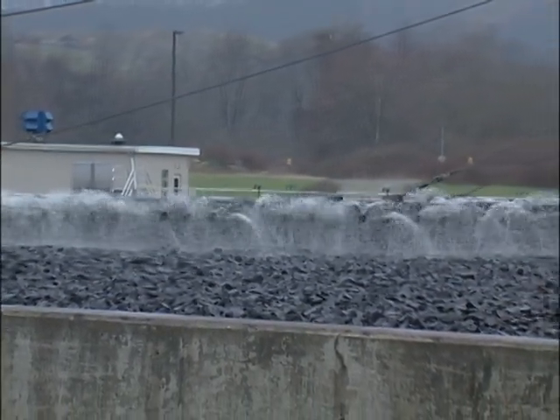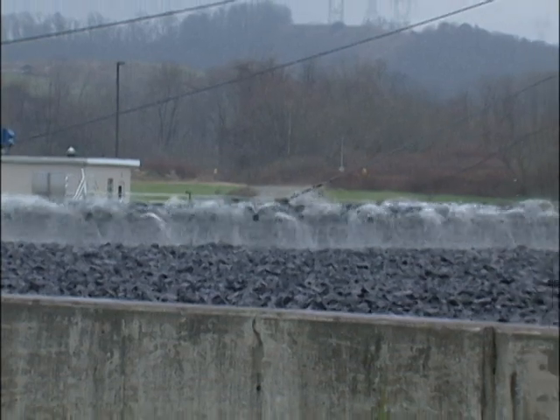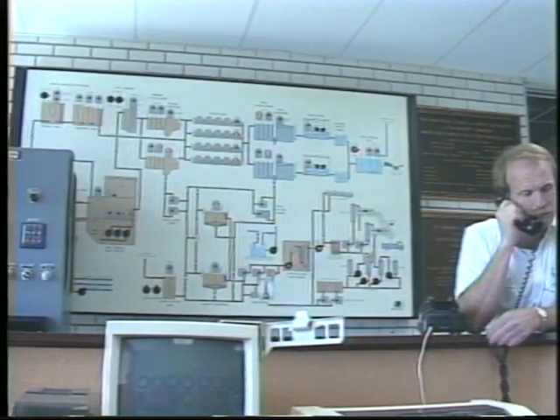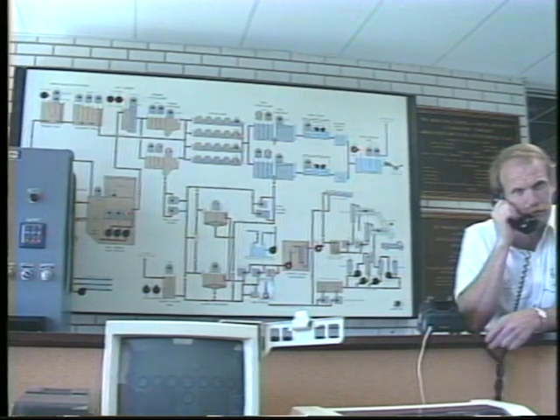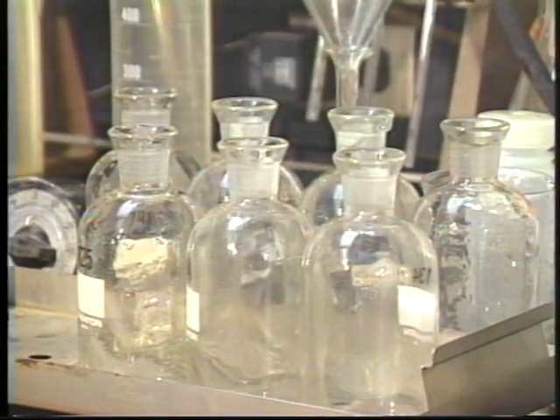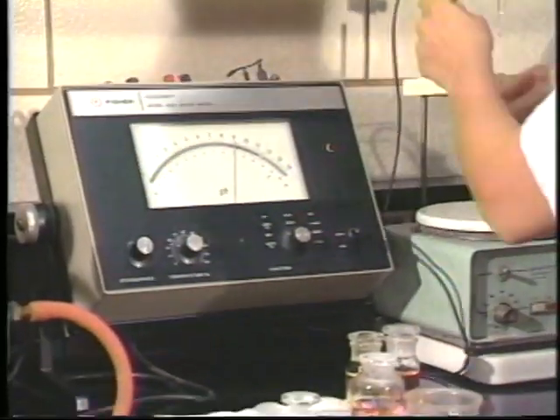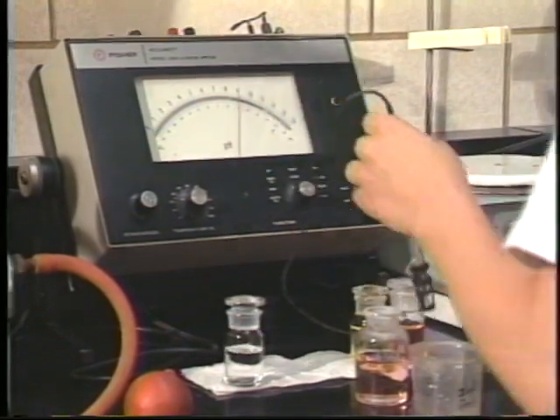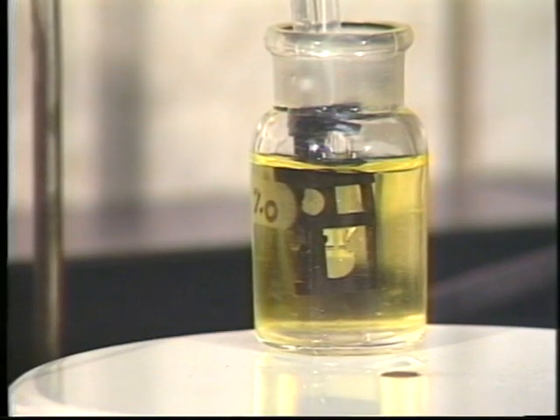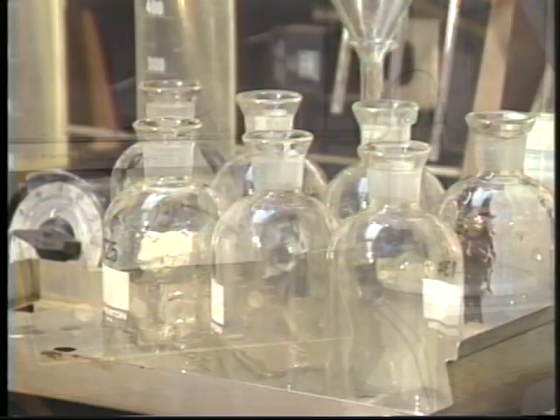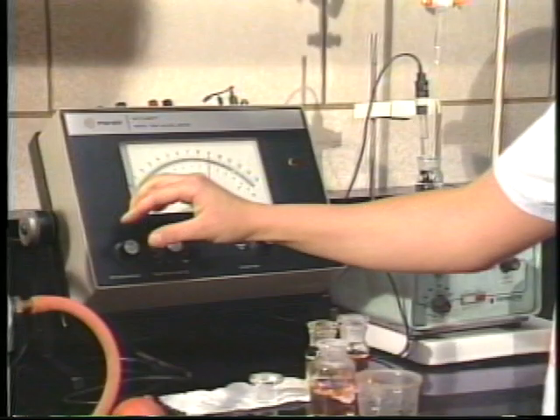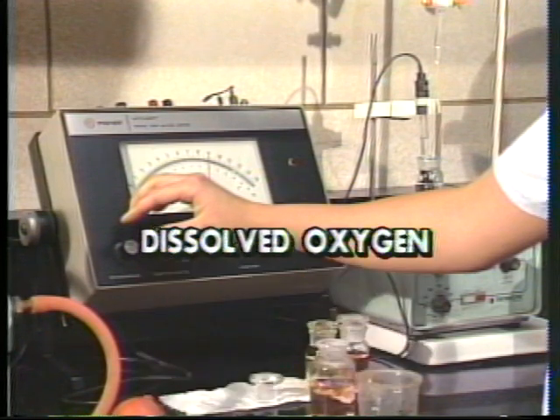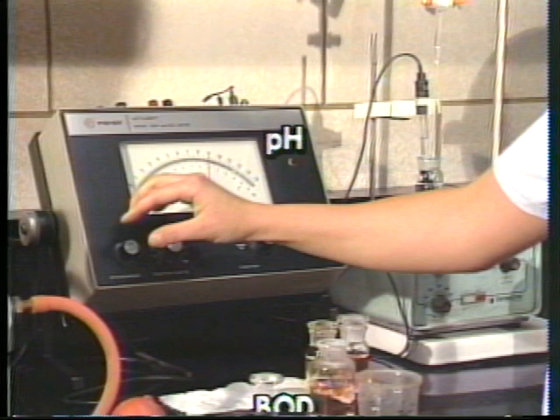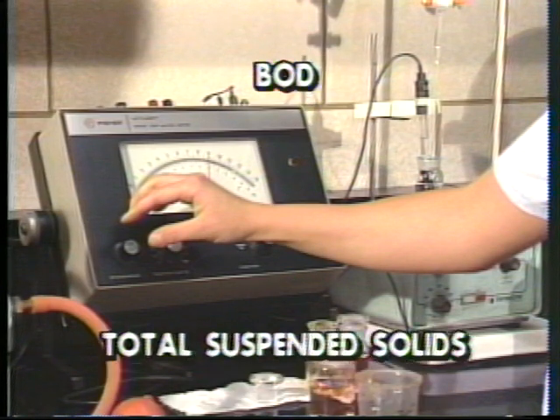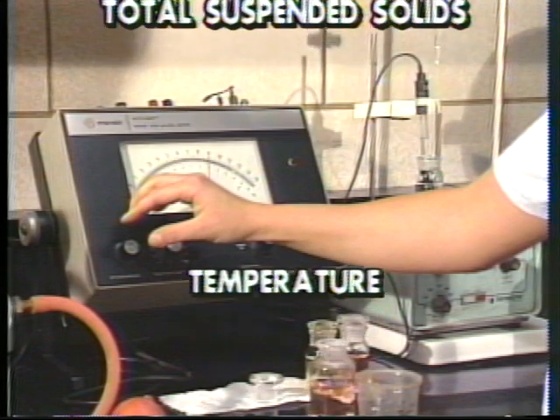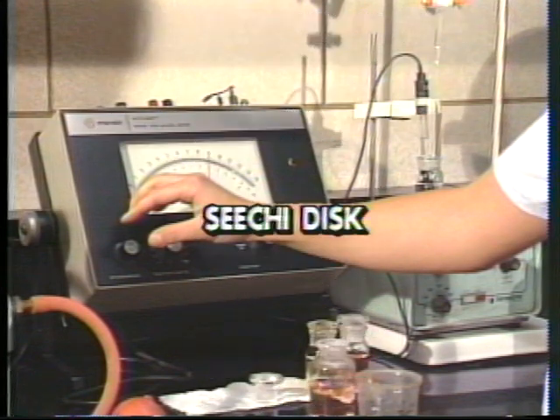At a well-operated treatment facility, the operator should be able to tell state or federal inspectors the efficiency, removals, and operational history of the treatment unit. In order to make proper process control decisions and calculate efficiencies, the facility operator must perform some process control testing on the influent and effluent of the trickling filter or RBC. At a minimum, the facility operator needs to perform the following process control tests: dissolved oxygen, pH, BOD, total suspended solids, temperature, Secchi disc in the clarifier.